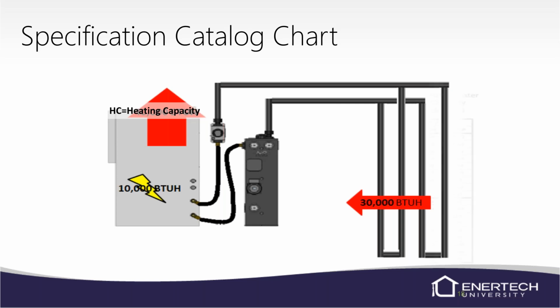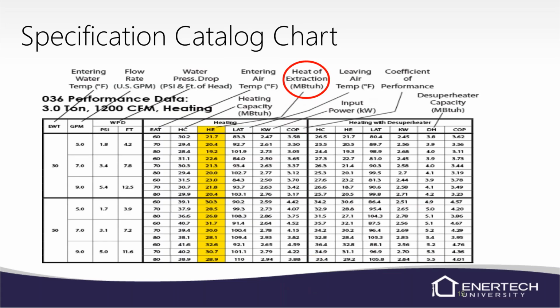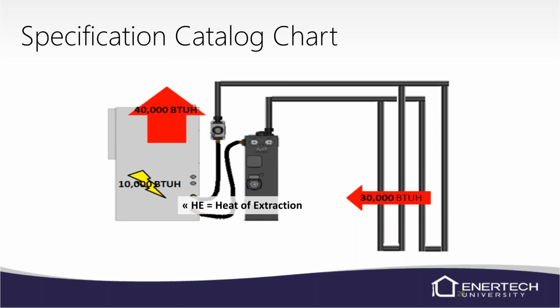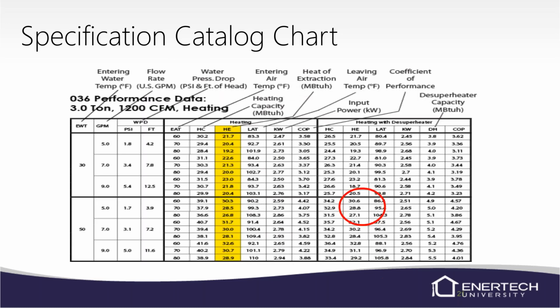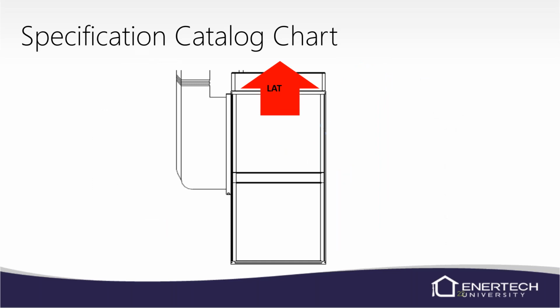With that number, we can also figure out your COPs and your EERs and how efficient the unit's actually running. But we do list heating capacities in there. Heat of extraction is just that, what we're pulling out of the loop field. So it's the amount of heat that we're extracting from the loop field. And that's what we're going to cover today. Leaving air temperature is the supply air temperature to the home. If you look at this chart on the very top one, at 30 degrees and 60 degree entering air temperature, the leaving air temperature should be roughly 83.3. So about a 23 degree temperature difference. We're normally somewhere in that range on the air side of 20 to 25 degrees. Again, leaving air temperature is your supply air temperature coming out of the top of the unit.